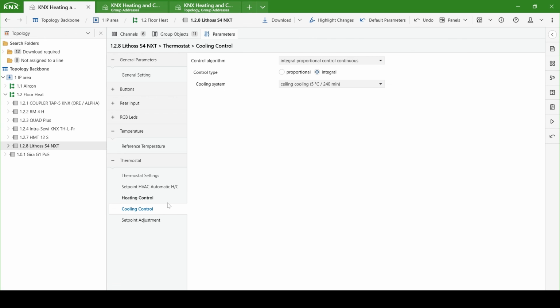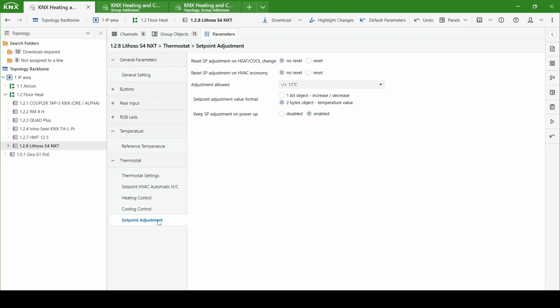And very similar with the cooling control. Set point adjustment is quite simple. We can allow how far they can adjust and how you want to see that. Do you want to see it in a 1-bit increase or decrease, or 2-byte float, which is standard?